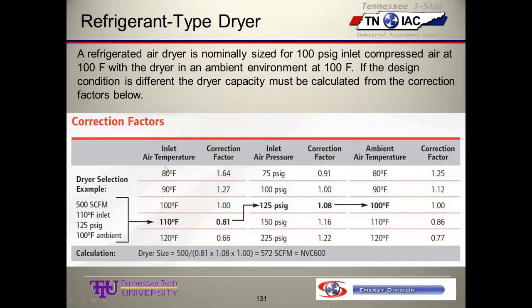So here's a correction for the inlet air temperature. At 110, we read a correction factor of 0.81. We file that away down here, which we'll put in our little equation. The 125 inlet pressure gets a correction factor of 1.08. That goes in the equation. And then the 100 degrees, that's the standard number, so there's no change. We get a correction factor of 1 for that.